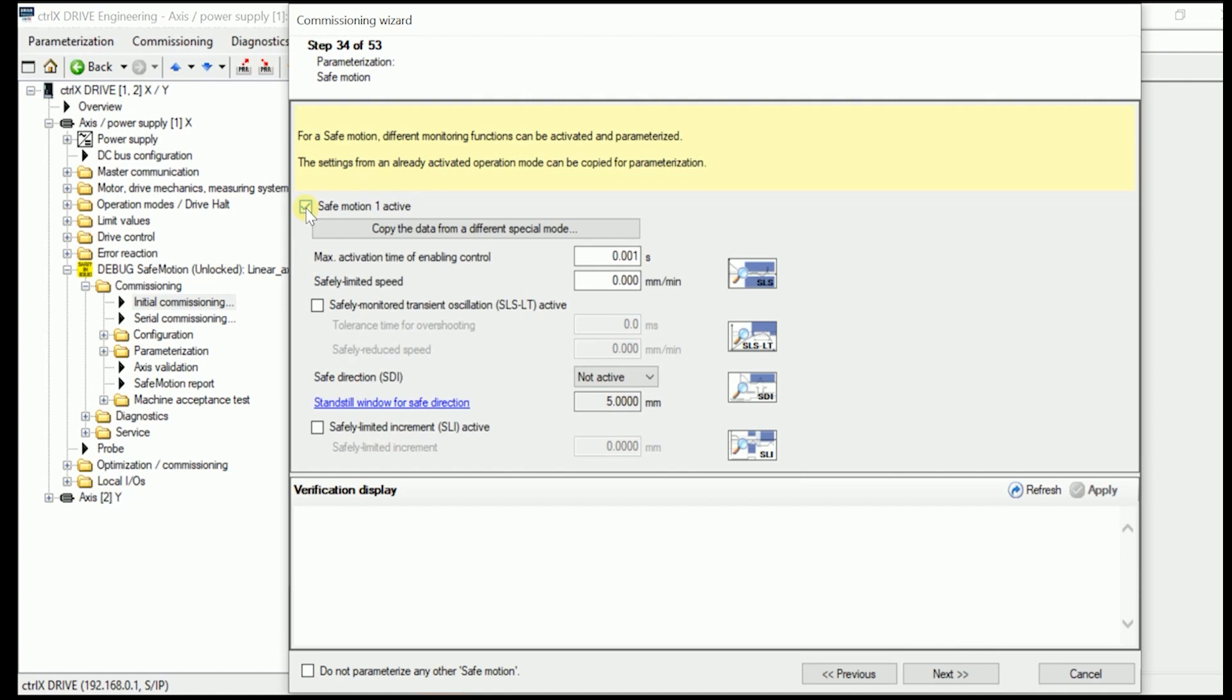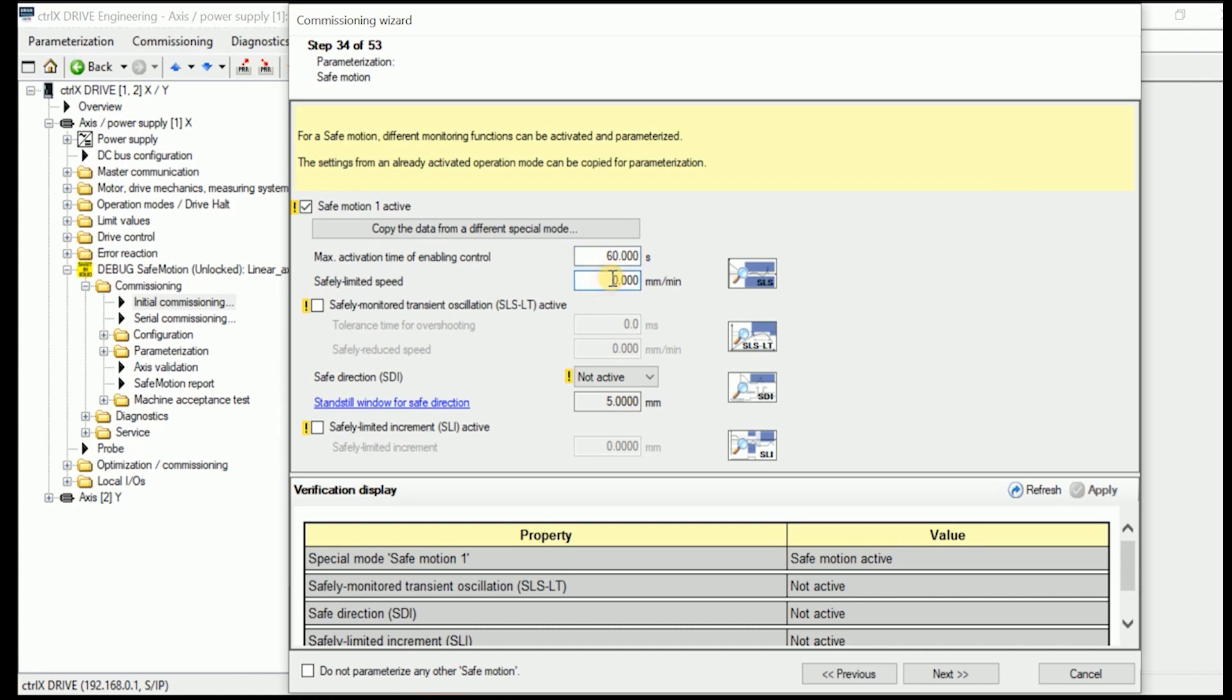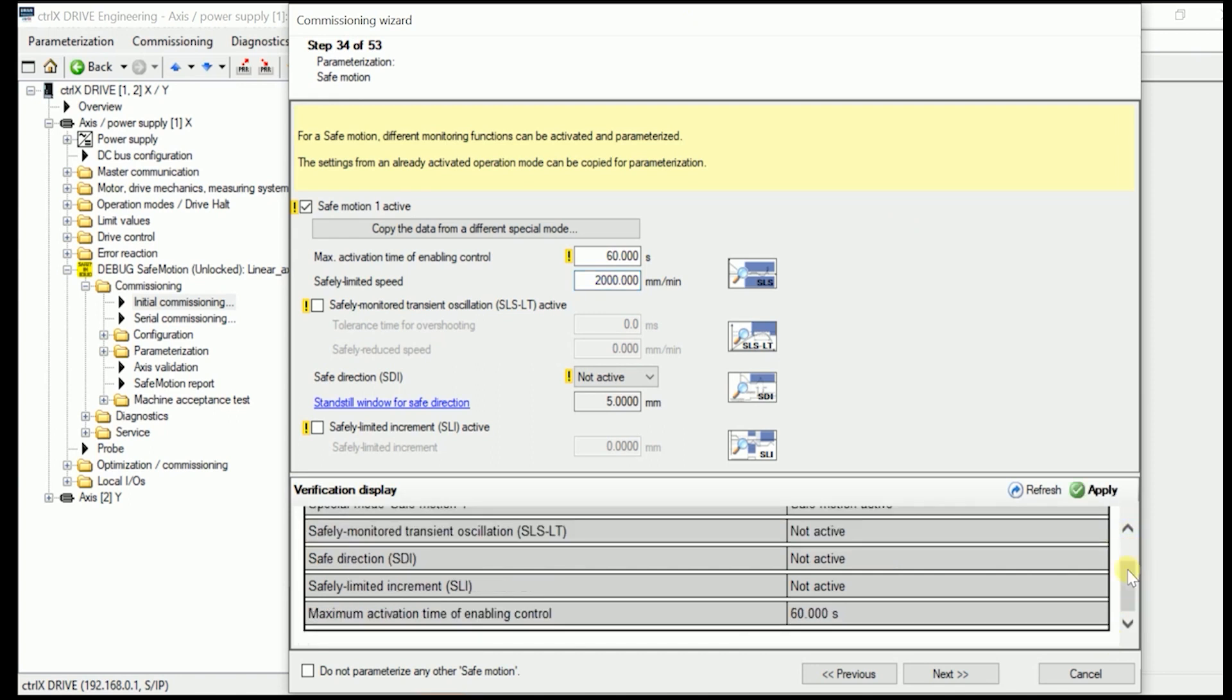As we made one safe motion active, we select in here how long longest I can press the enabling pendant signal. We put it now to 60 seconds. Usually as in here is the idea of making a machine tool axis work, we set the safe limited speed to 2000 millimeter per minute. We don't have any safely monitored transient oscillation or safe limited increment active. So we just apply these figures in here.